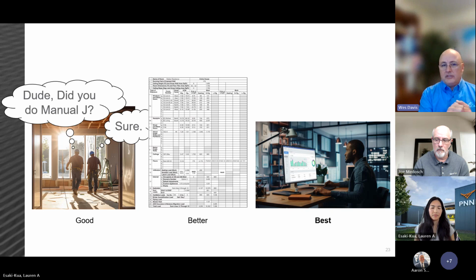But you can look at a few things. Is it your address or the right model home address on the Manual J? Look at things like floor area or window area. Do they match the home that's either being built or has been built? The best way, in my opinion, is to have someone that knows loads and knows plans look and see if the home being built or was built is accurately modeled in the Manual J software.